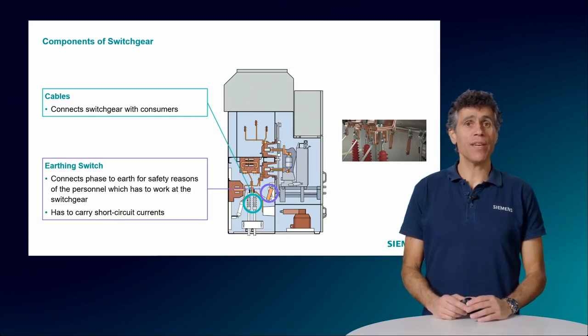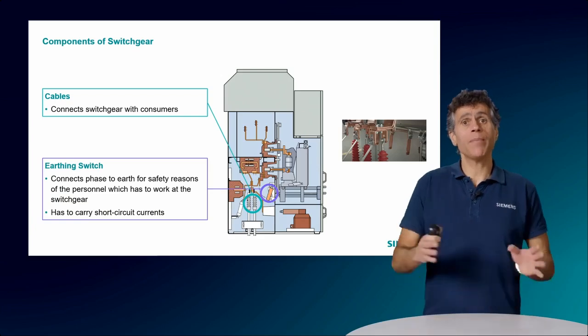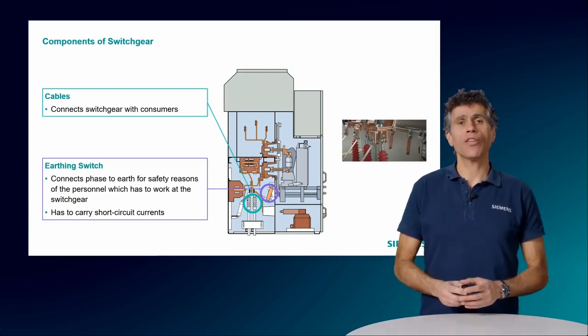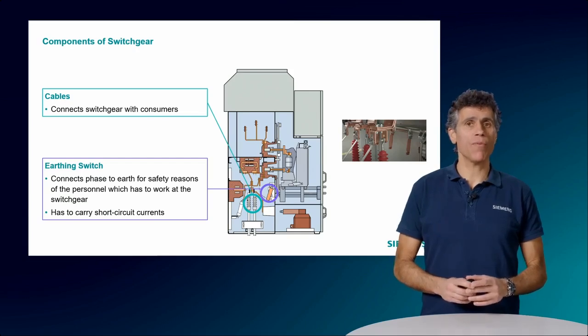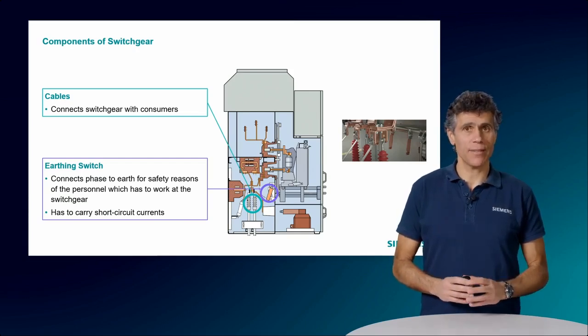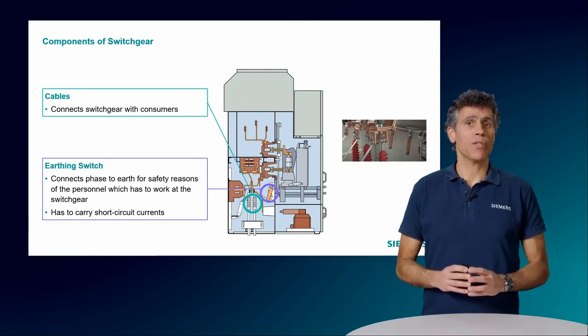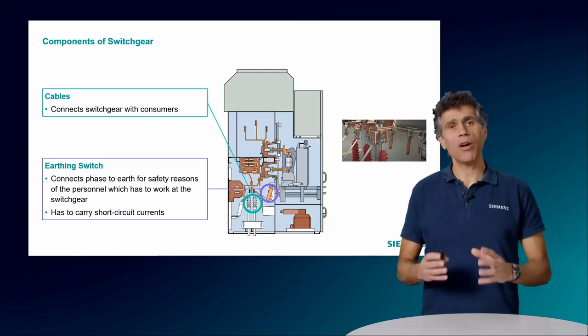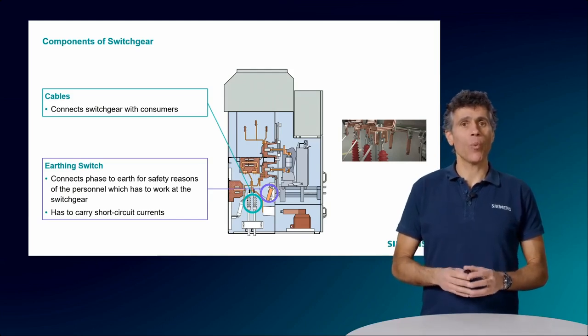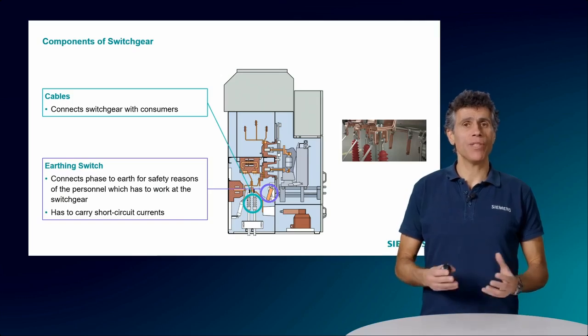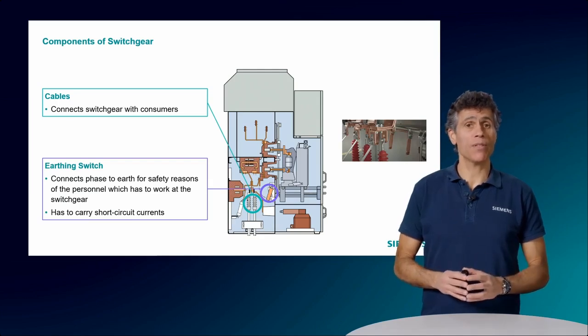The earthing switch is a very important component that connects the phases to earth. It usually connects each of the three phases to the earth and between them. It is used to make sure that an operator on the cable side cannot be exposed to voltage, even if power is turned on accidentally. You might think that we could do this by switching off the power with the circuit breaker. It's partially true, but it's not exactly the same. When you just switch off the circuit breaker, there can be residual capacitive voltages, which could harm an operator with a short but maybe powerful discharge. The earthing switch makes sure that the voltage is really zero and cannot harm anyone.